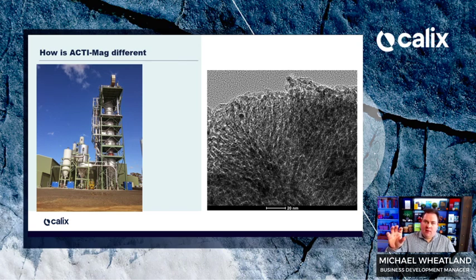The mechanism for capturing the struvite, capturing the phosphate particle actually inside the particle, is quite important for making sure that it doesn't deposit on pipes and things like that, and you can capture it in the sludge and it gets discharged with the sludge. So the high surface area of the ActiMag is very important when it comes to capturing phosphate.